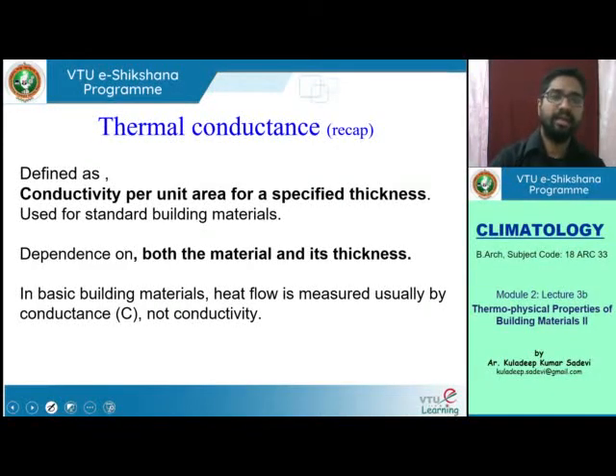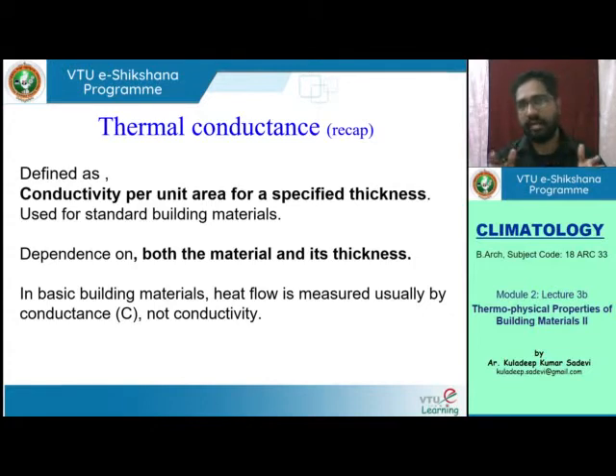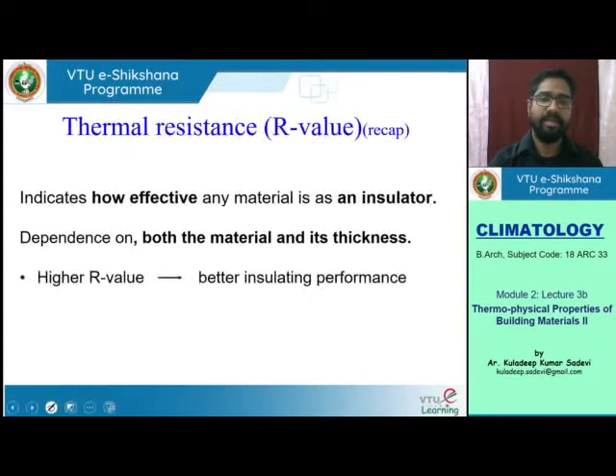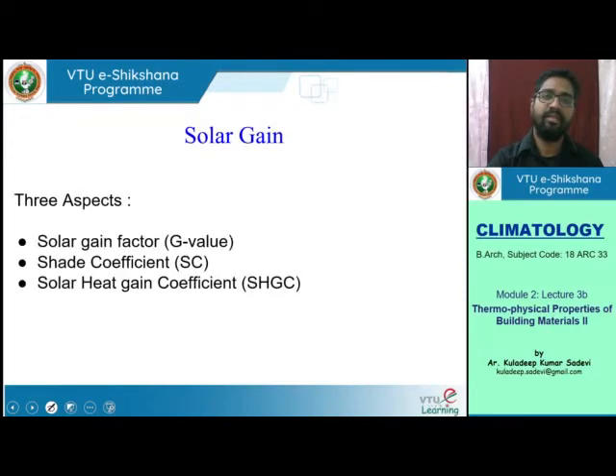Thermal conductance, as discussed in the last lecture, is conductivity per unit area of a specified thickness. The conductance of a 9-inch brick wall is different from that of a 4-inch brick wall, but the conductivity of both might be the same. Thermal resistance is 1 divided by conductance. Higher the R value, better the insulating performance.